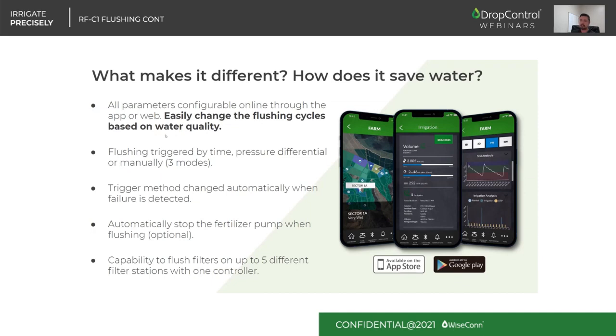The flushing could be triggered in 3 different modes. It could be by time, meaning that you can run a flushing cycle every 2 hours, every 4 hours, 6, 10, 12, whatever you desire. It could be triggered by the pressure differential, which we will need a sensor to do so. So you can have the typical pressure transducers before and after calculating the differential to trigger the cycle. You can have a Murphy switch, as we mentioned before, or you can have a specific pressure differential transducer.